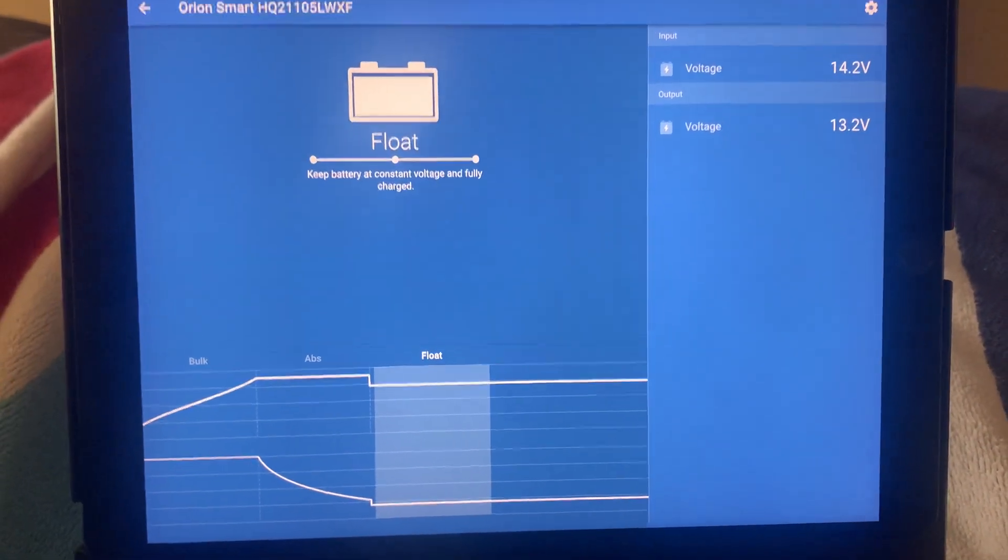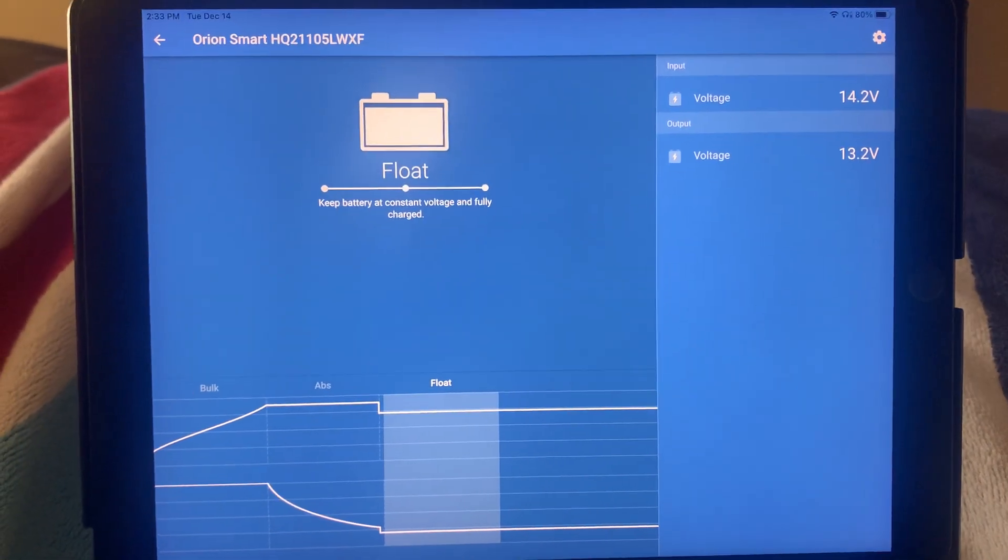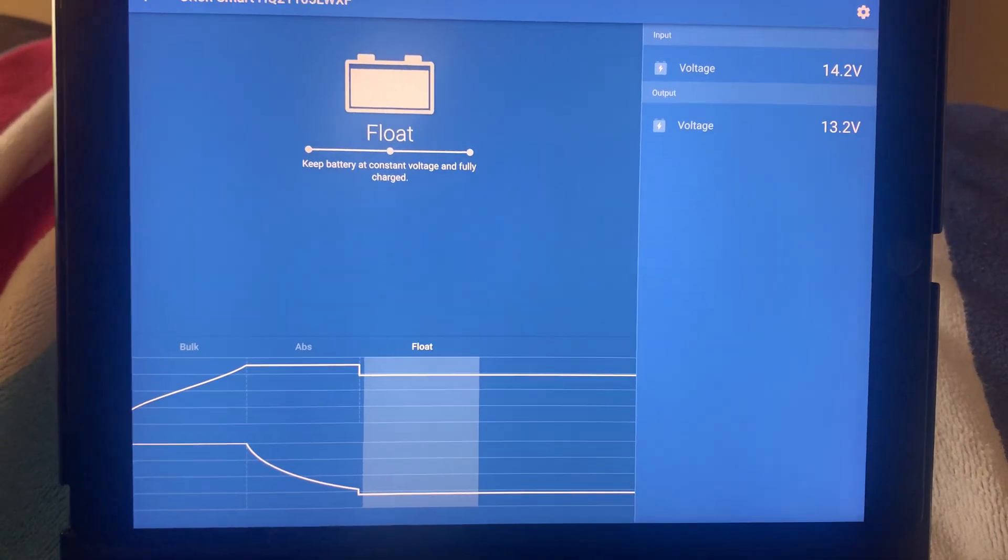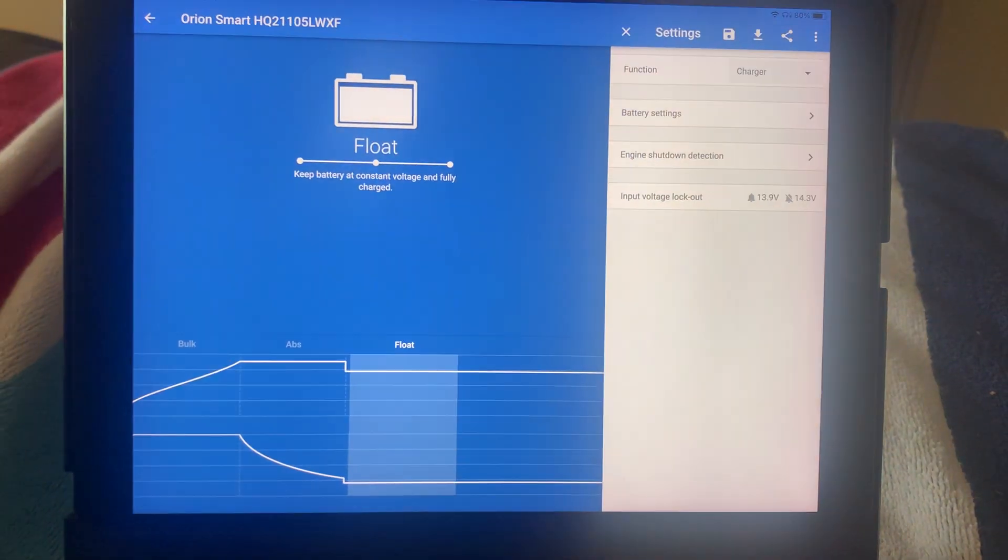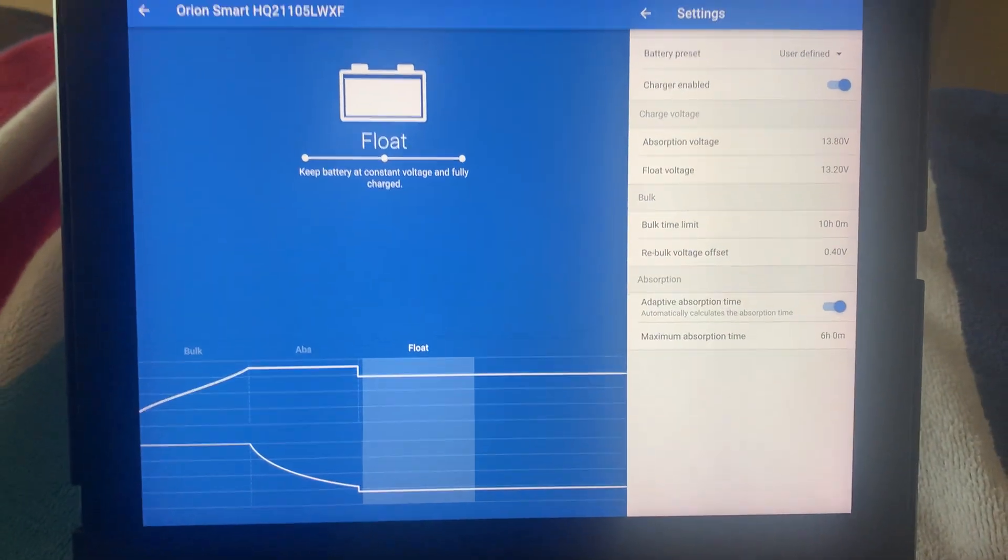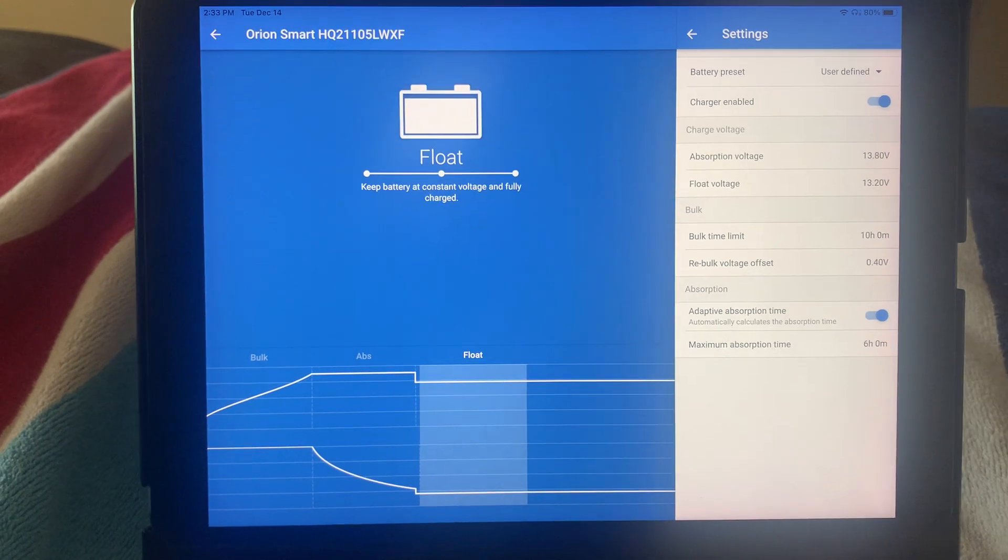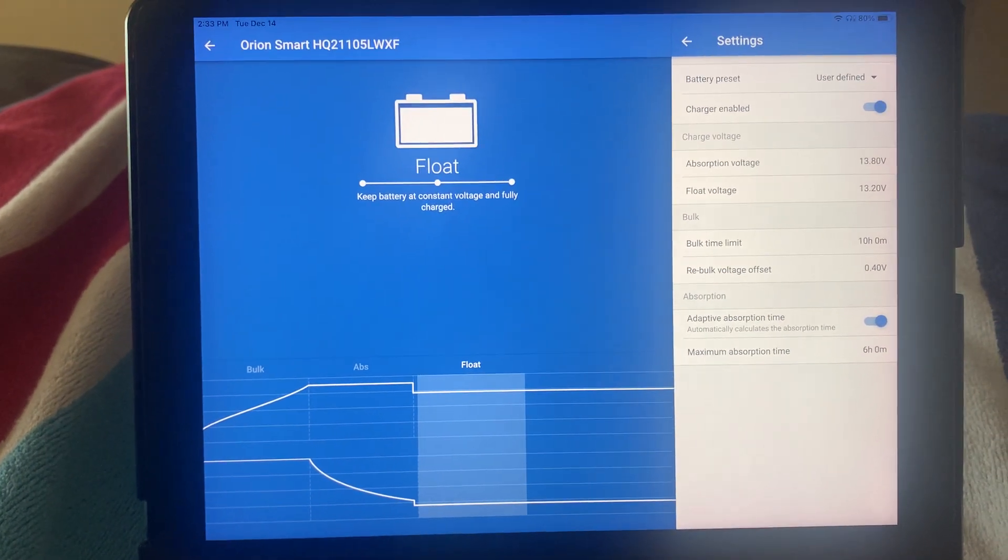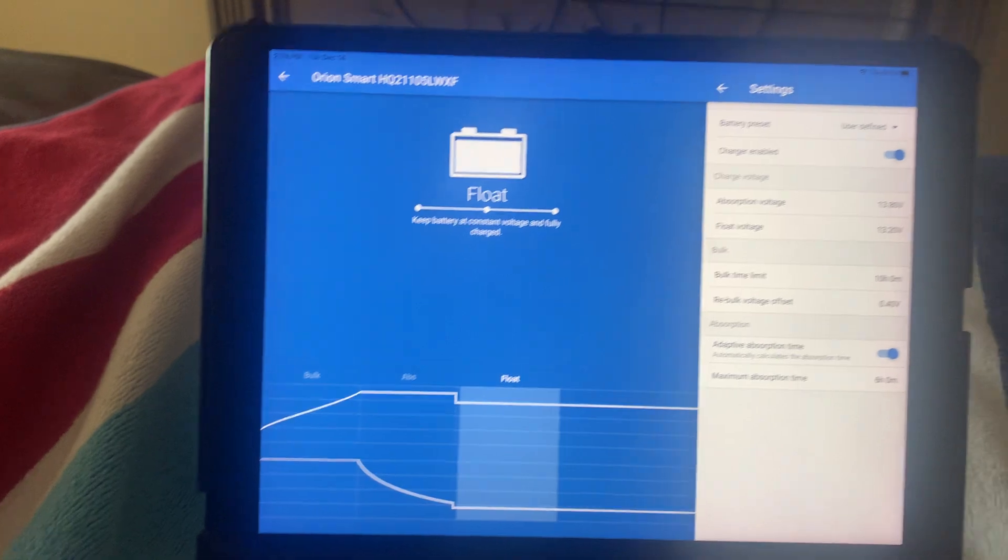Here's a quick review of how things are going with this Orion Charger. It's actually excellent. So I've set it up. I don't want this thing kicking in unless my primary batteries are full. So what I did is I've set it up with the AGM battery parameters here, a little bit light, saying 13.2 for float and 13.8 for absorption. But the important thing is this.